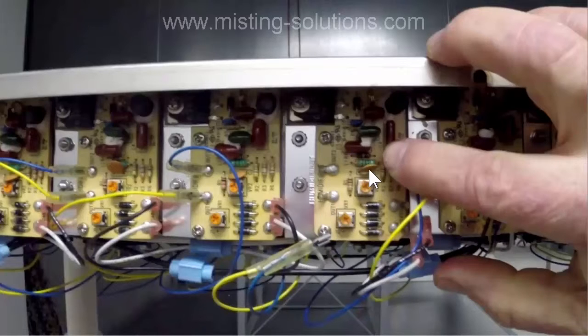But not all the boards have that happen. Sometimes it's the board that fails, sometimes it's the actual nebulizer transducer. When you repair them, it's wise to just replace them both - not that it's really wise, it's just too time consuming to troubleshoot and determine whether it's the board, the transducer, or both. If you get a whole new set and put them in, you know it's going to work, and you know you've got fresh components in that spot.